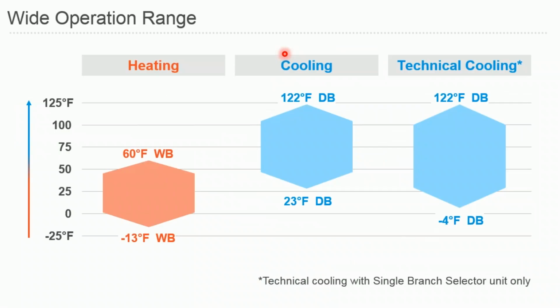From an operation range standpoint, again, it stays the same as VRV4. For heating, you're limited to -13 degrees Fahrenheit. On the cooling side, the upper limit is 122. And if you want to do technical cooling below 23 degrees Fahrenheit dry bulb temperature, you can go down to -4 with the technical cooling function, which is already available with VRV4 heat recovery models. And all the rules still stay the same for technical cooling, things like using single branch selector boxes only, that is still applicable to VRV4X.